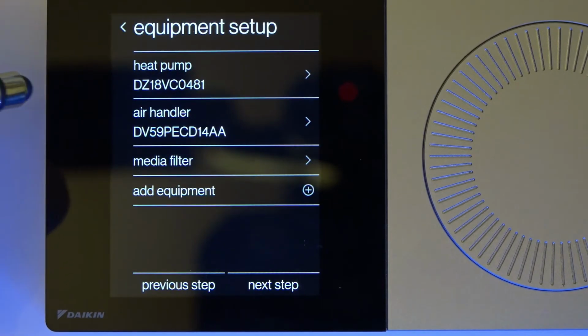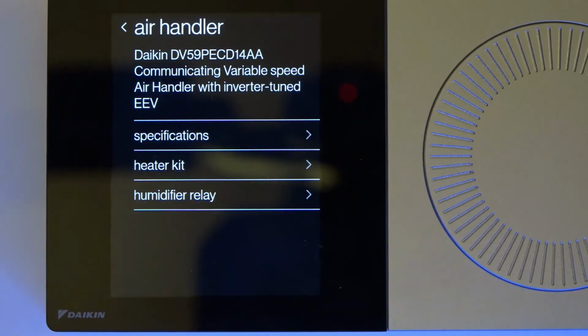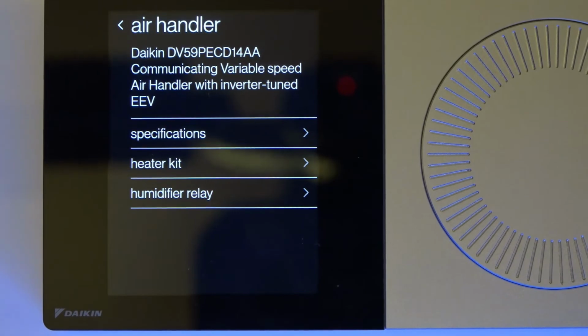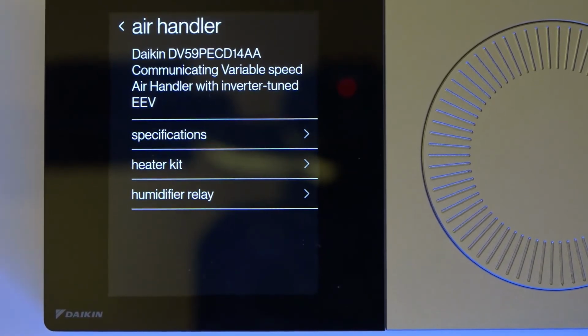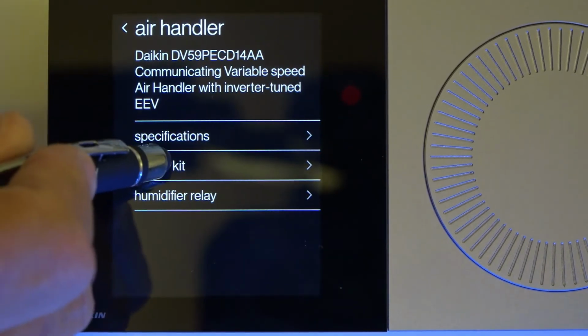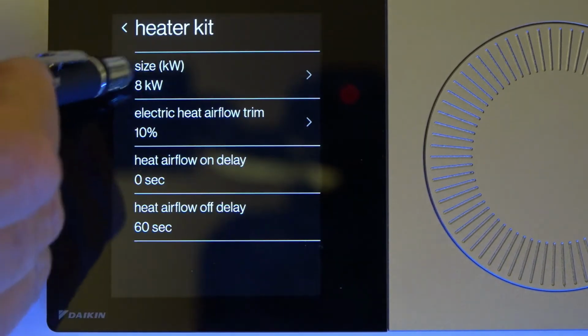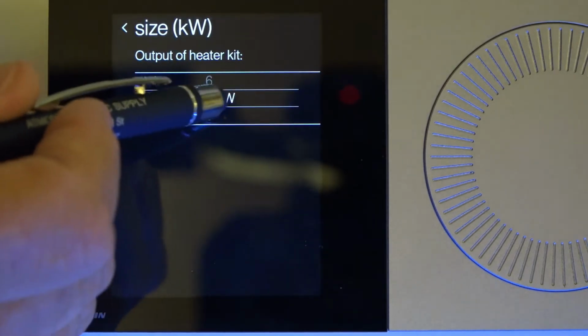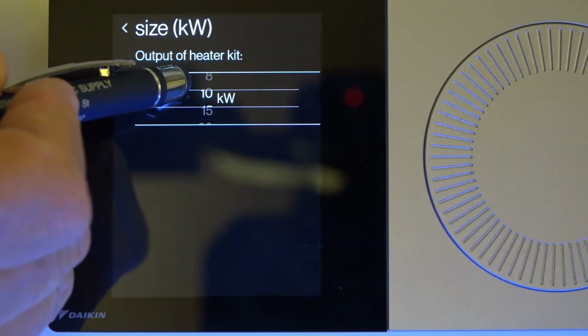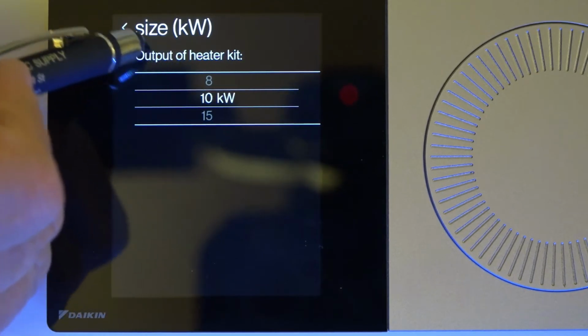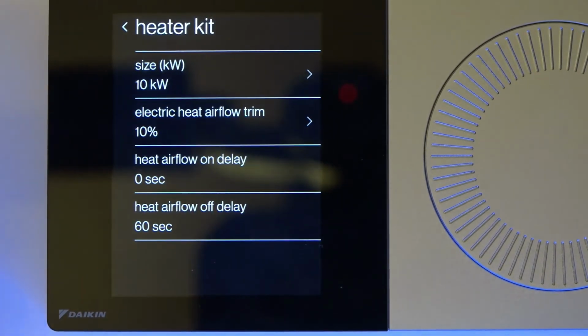Now let's back up so we can see the air handler. Under the air handler, I have to specify what kW heater is in this air handler, because if we don't tell it how much kW is in it, it will never, ever, ever turn it on. So I can come over here, heat kit, and select my kW. I've got it selected at 8. Let's change that to 10. I've got a 10 kW heater in there.